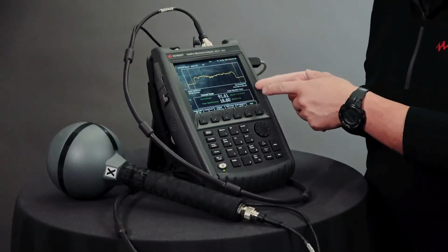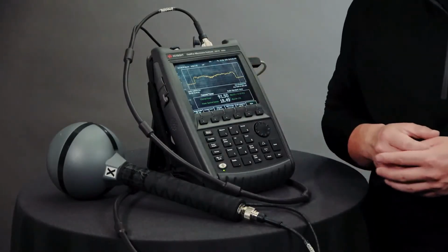So there are different standards coming from WHO, FCC, or various regulators around the world. The requirement is that you have to use an isotropic antenna, which is built like a triaxial antenna, which has 3 axes, X, Y, Z. They are individually polarized. So we basically create an antenna pattern, which is kind of like a ball, and every direction has the same gain. Then we take the data and make a channel power measurement and convert that into field strength.